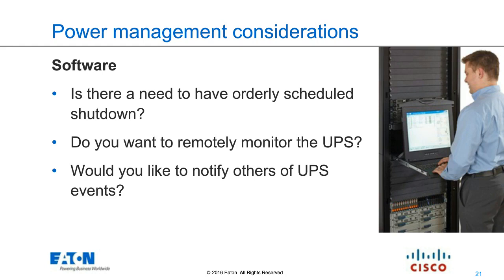We can do clever things like trigger a specific migration of groups of VMs from one environment to another, and we can power cap Cisco UCS platforms through UCS Manager. Since the UPS battery has limited chemical storage, to extend that, all you need to do is reduce the actual wattage. Cisco's power capping functionality is great for this, because rather than shutting workloads down, we can just slow everything down a little, reducing power supply demand on the UPS and extending runtime, giving you a better chance of riding through the event.